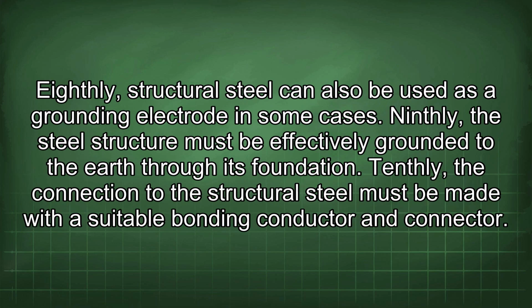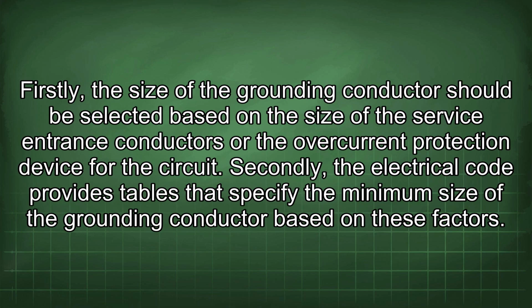Eighthly, structural steel can also be used as a grounding electrode in some cases. Ninthly, the steel structure must be effectively grounded to the earth through its foundation. Tenthly, the connection to the structural steel must be made with a suitable bonding conductor and connector. Firstly, the size of the grounding conductor should be selected based on the size of the service entrance conductors or the overcurrent protection device for the circuit.